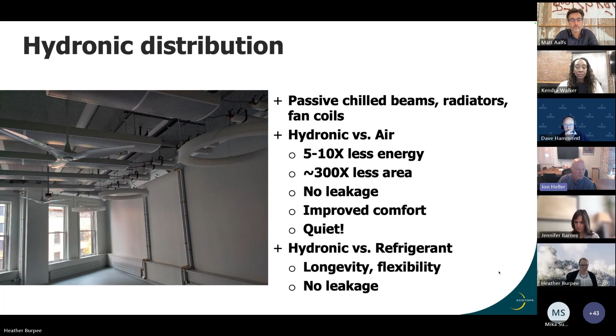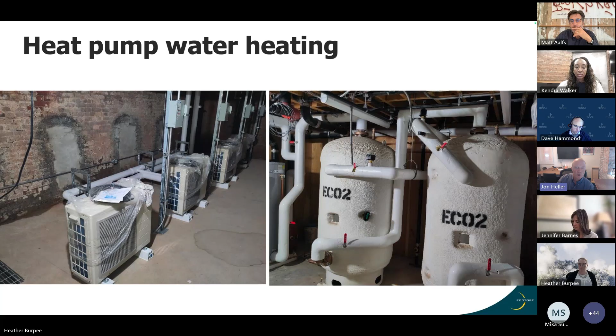We're also using heat pumps for heating water for the commercial kitchen and showers in the building. Again, we're using multiple small stages with one redundant heat pump. It looks like there's 4 heat pumps in that picture, but one of those is for the elevator machine room. So there's three small heat pumps for the hot water system. And then large thermal storage tanks, again, which provide for long cycles of the heat pumps, which the heat pump equipment likes, and also allows for load shifting off of peak utility times with that thermal storage.